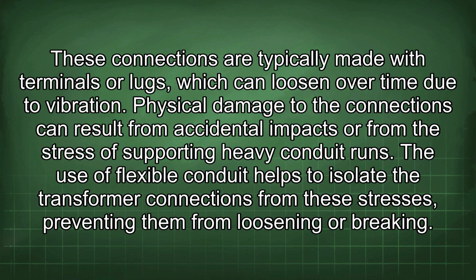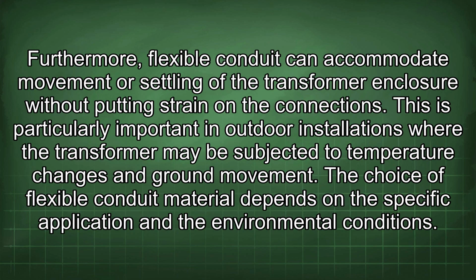The use of flexible conduit helps to isolate the transformer connections from these stresses, preventing them from loosening or breaking. Furthermore, flexible conduit can accommodate movement or settling of the transformer enclosure without putting strain on the connections. This is particularly important in outdoor installations where the transformer may be subjected to temperature changes and ground movement.